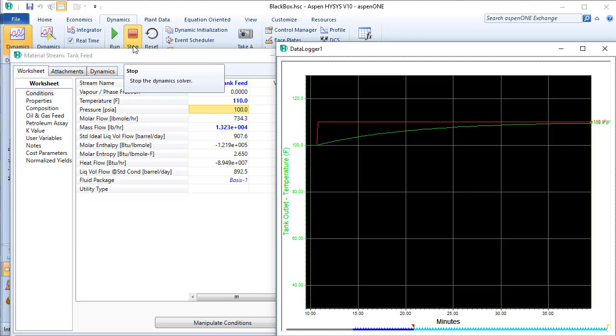Now, let's calculate tau, the time constant for the process. It looks like the process hit 63% right around here, which is 10 minutes after the step change. If the data was noisy, we'd have to use other methods to estimate tau, but since the response is clean, we can use 10 minutes for tau.